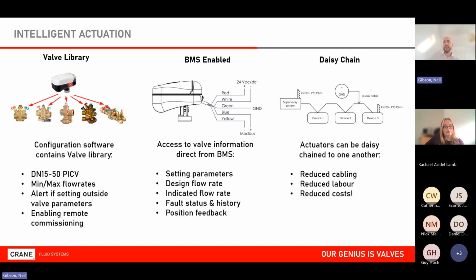And when we think, what's the benefit of that? For any given valve, I've got my flow rate information built in there as well. So I can select, say, a 2-inch PICV that I'm connected to. I screw it onto a 2-inch PICV, that one in the middle. And when I say I'm on that PICV, it'll give me the flow range. I input the flow range on a separate Modbus register. The valve will drive to that flow. I didn't have to physically touch the valve in any way, apart from screwing the actuator on. I don't have to go to it. I don't have to check it. All I have to do via the BMS is set the flow rate.